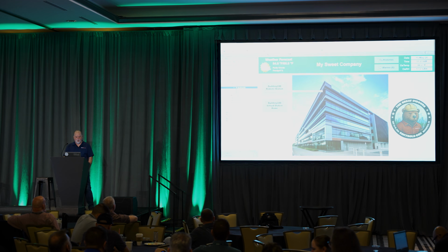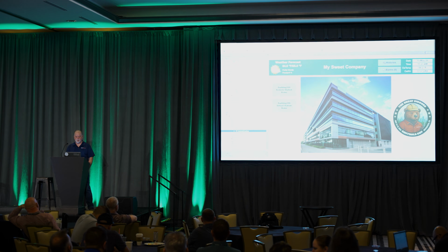Good? Okay. So you can see under the Niagara network of my supervisor, I'm only talking to this building 100 station, but when I go look at the building 100 station at its Niagara network, then it's going to be communicating with that supervisor, but it's also communicating with another building, okay? So my campus supervisor doesn't have a direct path to that, but we can get to it through the Niagara virtuals of the other station. So that's one of the key aspects of that multi-tiered system database, and also the multi-tier on the security dashboard as well, okay?